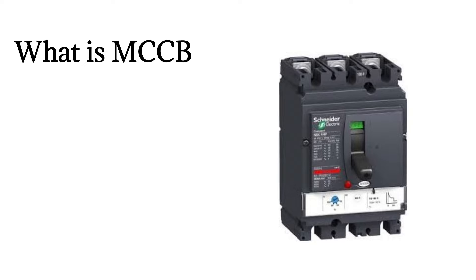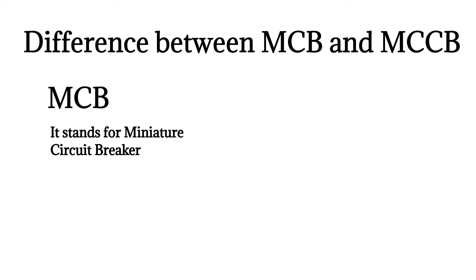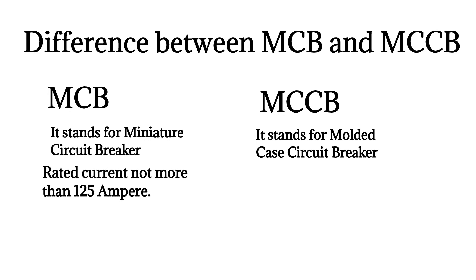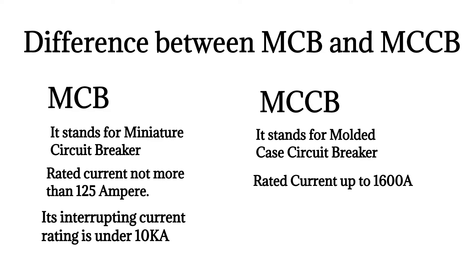MCCB offers adequate protection whenever an application requires discrimination, adjustable overload setting, or earth fault protection. Comparing MCB and MCCB: MCB stands for Miniature Circuit Breaker; MCCB stands for Molded Case Circuit Breaker. MCB has a rated current of not more than 125 amperes, while MCCB has a rated current up to 1600 A. The interrupting current rating of MCB is under 10 kilo-amperes, whereas MCCB interrupting current ranges from around 10 kilo-amperes to 85 kilo-amperes.